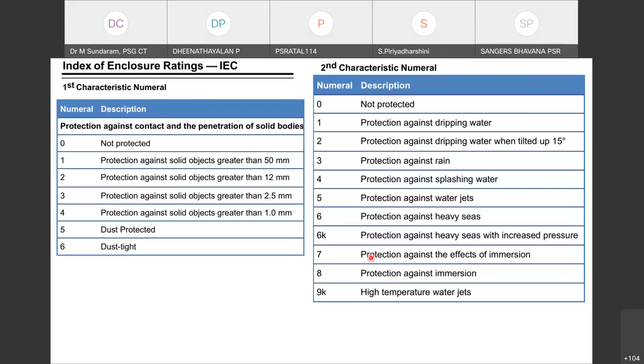Then there's IP protection: the first digit is for solid bodies, the second is for water. For instance, IP57 means protected against the effects of immersion—'5' indicates just protected. When you keep your machine in the atmosphere, IP57 may be enough, but sometimes people go for IP60, 65, or 67. So this number is important.